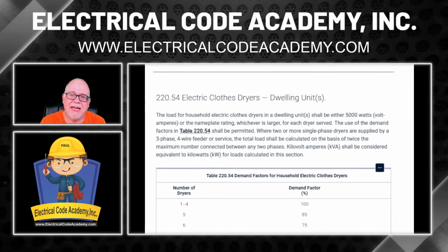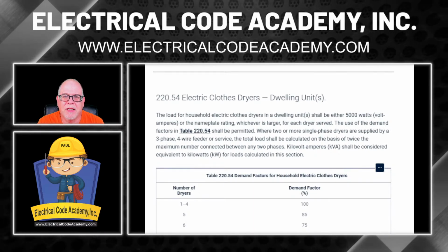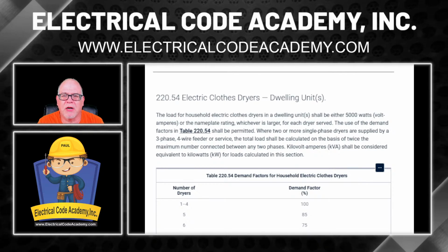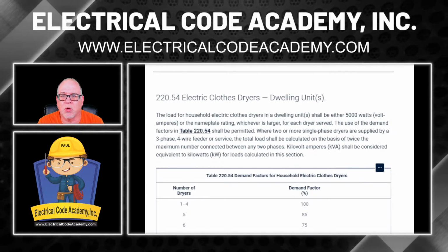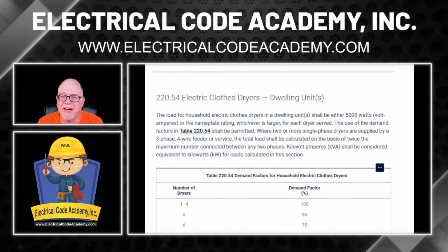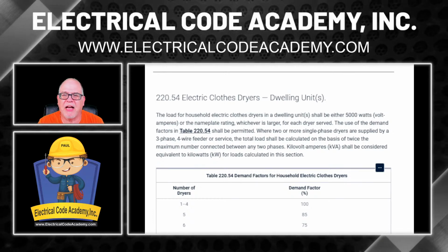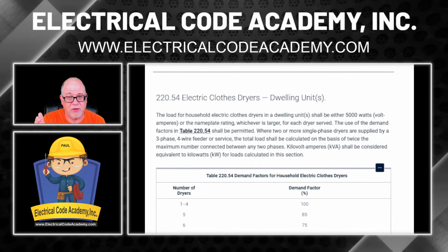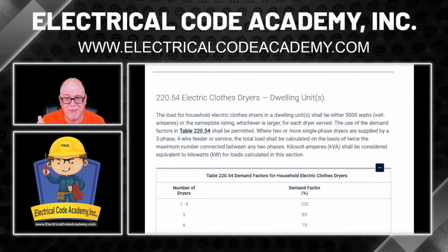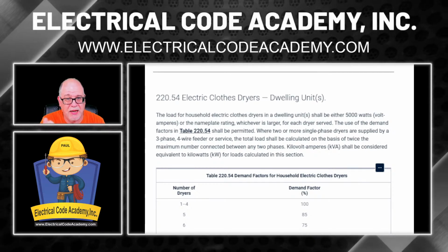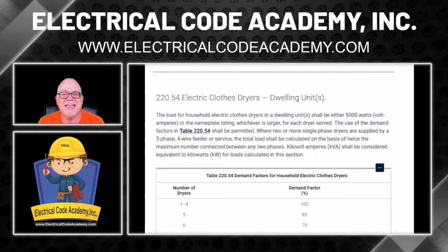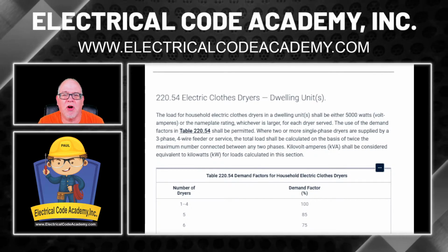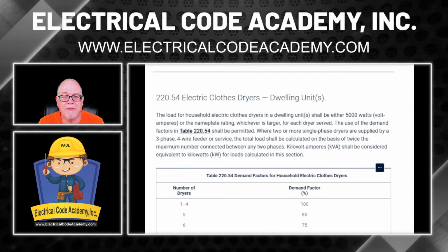All right, so look right here. 220.54. It says the load for household electric clothes dryers in a dwelling unit, or units, so we only have one we're dealing with right here, shall be either 5,000 watts, and obviously you see it says volt amperes. It's synonymous, 5,000 watts or 5,000 VA, or the nameplate rating, whichever is larger for each dryer served.